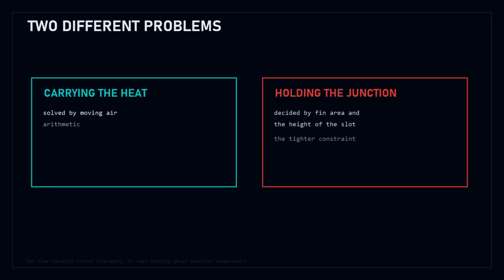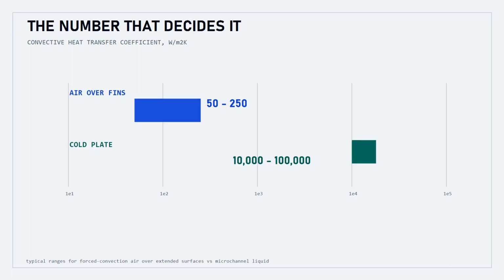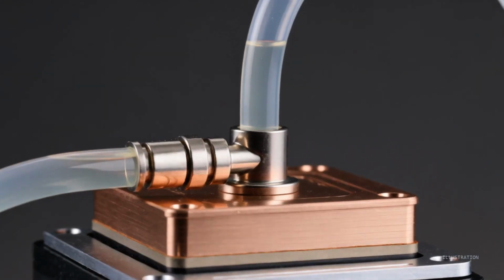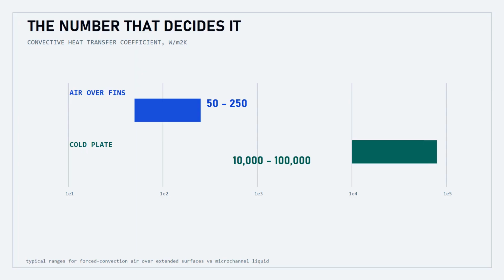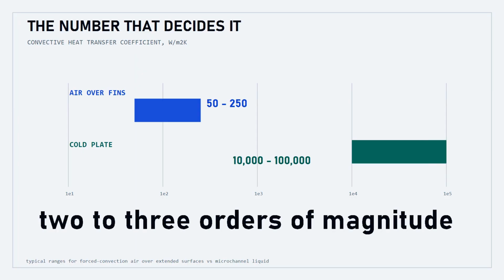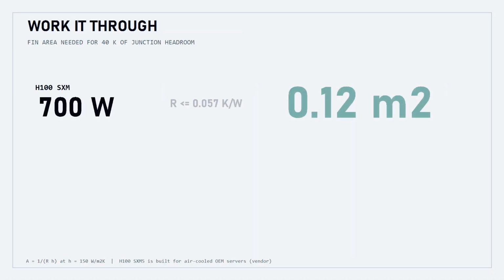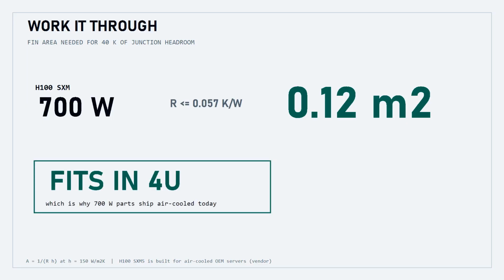But carrying heat and holding a chip below its limit are two different problems. And I very nearly published only the first one. The number that decides it is the heat transfer coefficient. Air over fins gives you 50 to 250 watts per square meter per Kelvin. A cold plate gives 10,000 to 100,000. Work it through. A 700 watt H100 with 40 Kelvin of headroom needs 0.12 square meters of fin. That fits in 4 rack units, which is why those ship air cooled today.